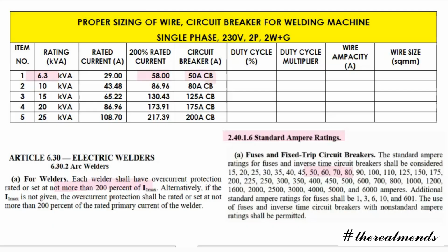Okay, so for 10 kVA we have 86.96 amperes. So look at the PEC. It falls between 80 and 90. If we use 90, we will exceed the code, so it should be not more than that. So let's use 80 amperes. For 15 kVA we have 130.43 amperes. Look at the PEC, there is no 130 amperes here, but we have 125. So we use a 125 ampere circuit breaker.